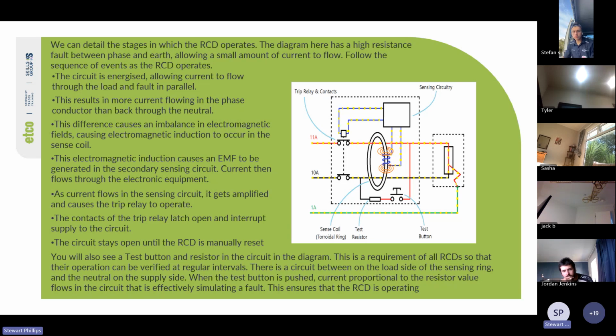So yeah, we talked about the test button with the resistor in the circuit diagram. This is a requirement for all RCDs, so the operation can be verified at regular intervals. There's a circuit between the load side and the sensing ring and the neutral on the supply side. When the test button is pushed, a current proportional to the resistor value flows in the circuit. It's effectively simulating a fault. This ensures that the RCD is operating. So it is just a functionality test. It does not count as doing an operational test. You still need to do your operational test to ensure trip time and the trip current.